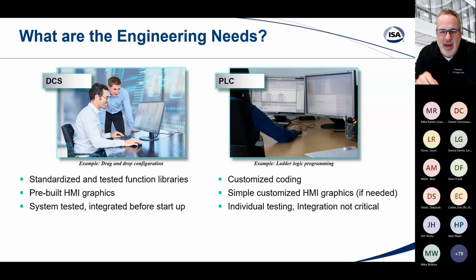And so now when you're on the HMI side, all you have to do is click on that, and that'll open up a pre-designed faceplate where you have all the information available for that particular process or automation or function. And again, on the PLC side, typically not required, so they have more, generally simpler, customized HMI graphics if even necessary. The other thing on the DCS side is everything is all tested before startup. You could have multiple controllers, multiple servers, multiple OS stations or HMIs, and everything has to work in harmony before you can even go to startup.